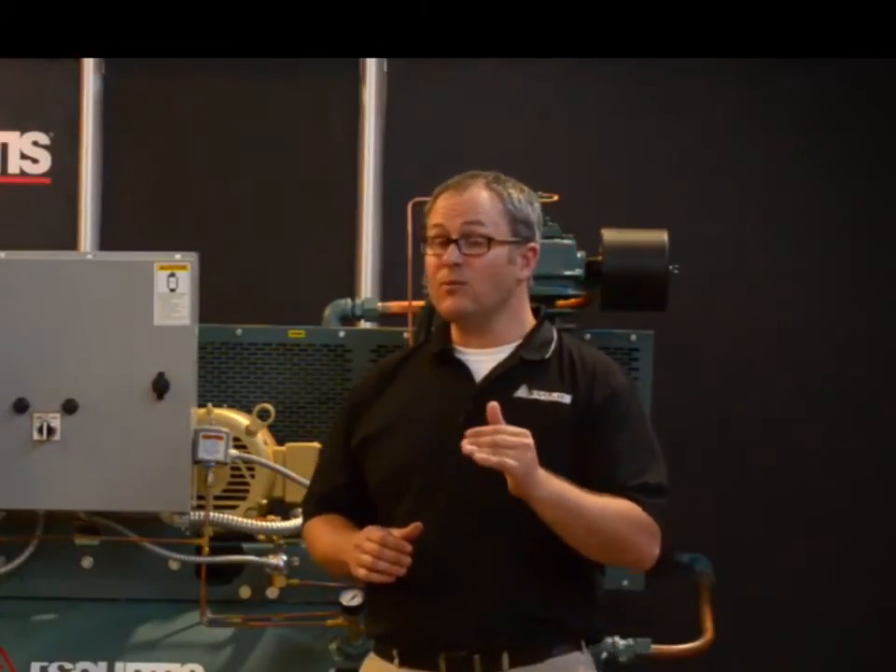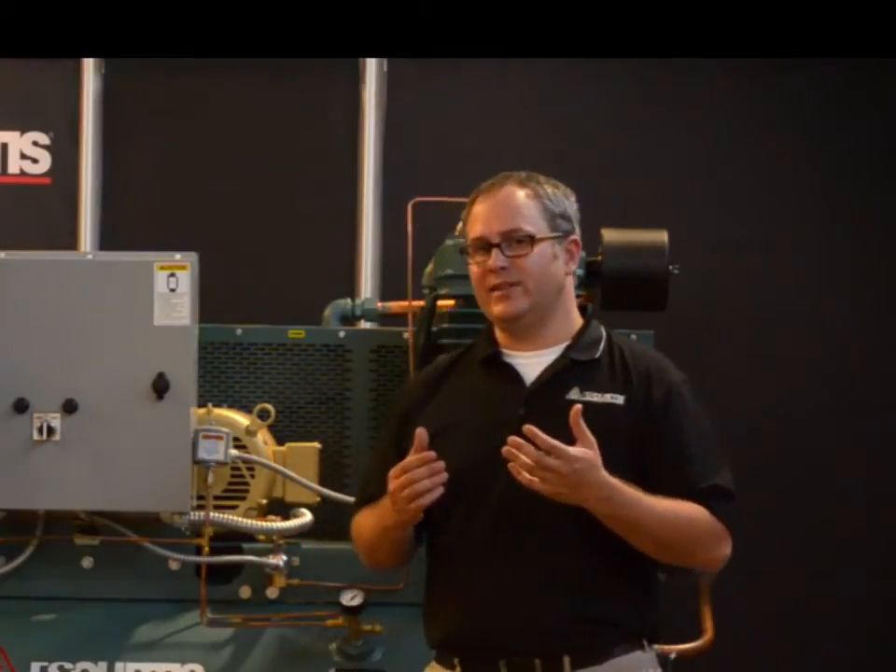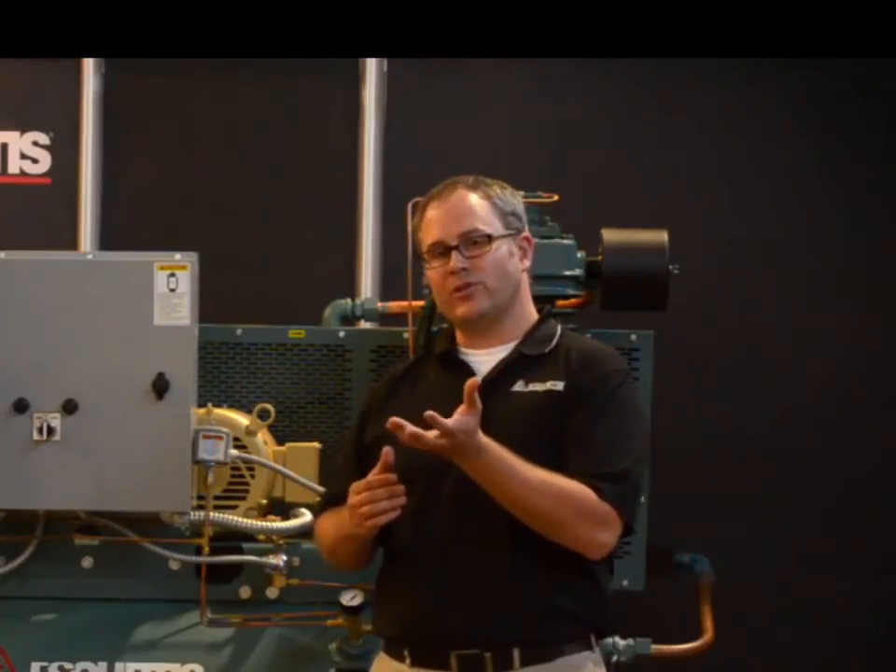Some of the things you'll want to watch out for with rotary screw technology is that they are more expensive than reciprocating compressors, as Matt mentioned, but you've got to weigh that against the life of the compressor. Also, maintenance is more critical — rotary screw compressors require a little more maintenance attention, and the maintenance may not be as familiar as with reciprocating technology. There is also risk in oversizing these units, where you could oversize a reciprocating compressor and grow into it, but with a lower duty cycle there are problems that can occur with a rotary screw compressor.